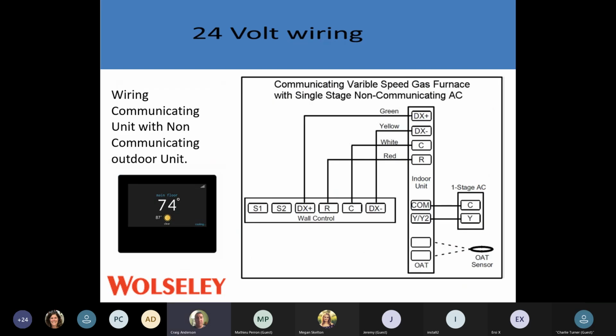If you're working on a communicating unit and the outdoor unit is not communicating, we can connect that to our board downstairs. We're not going to be using the green plug. We're going to go right to our board on our furnace. So if you're adding on an air conditioner that is non-communicating to a communicating system, you are going to go back up to that stat and you're going to have to relearn that stat. Relearning that stat is going to allow the stat to look for equipment again, because it wasn't programmed into that stat.